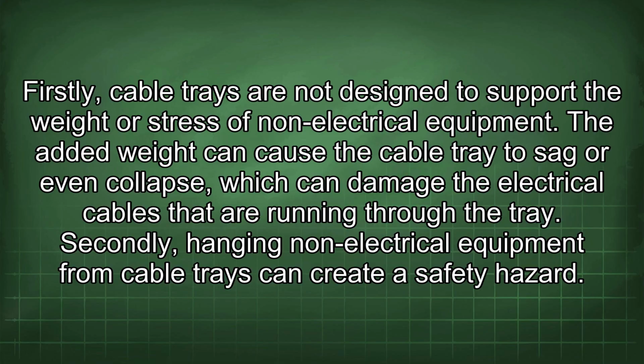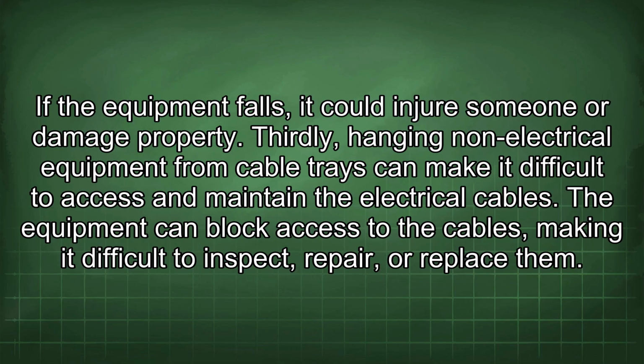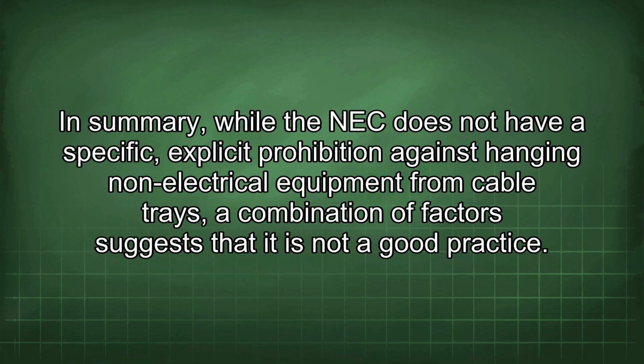Secondly, hanging non-electrical equipment from cable trays can create a safety hazard. If the equipment falls, it could injure someone or damage property. Thirdly, hanging non-electrical equipment from cable trays can make it difficult to access and maintain the electrical cables. The equipment can block access to the cables, making it difficult to inspect, repair, or replace them. In summary, while the NEC does not have a specific, explicit prohibition against hanging non-electrical equipment from cable trays, a combination of factors suggests that it is not a good practice.